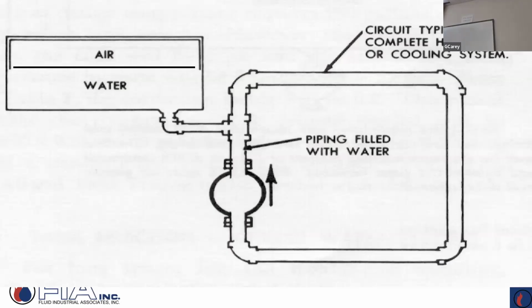So really very simple. This is why it is what it is, if you will. So we're saying, you know, very simple little piping connected to an old style tank, because when he wrote the paper, old tanks. Today we'll replace it with a diaphragm, and it's the same principle. And what he's saying here is, I've got this system completely filled with water and a pump and my expansion tank.